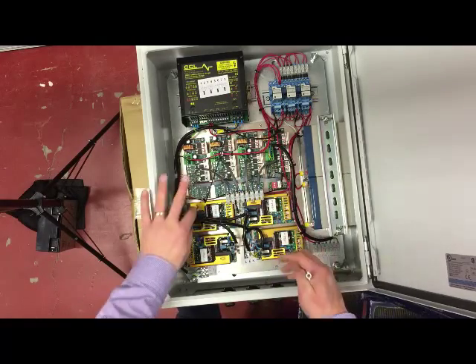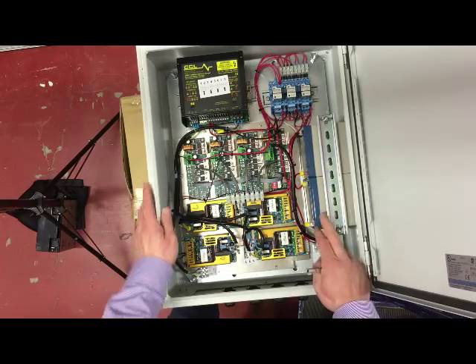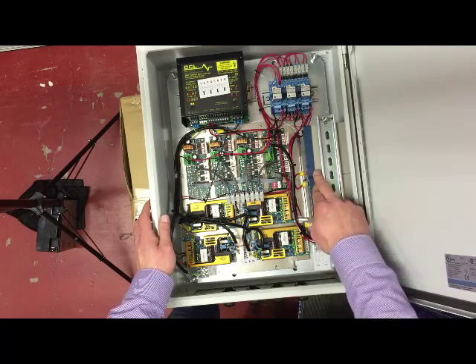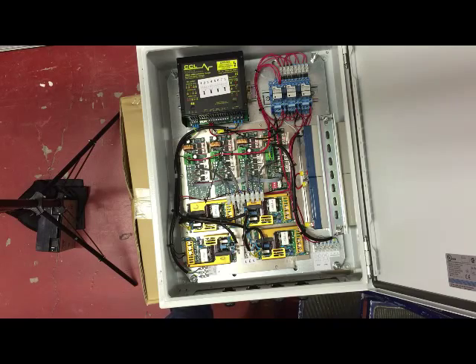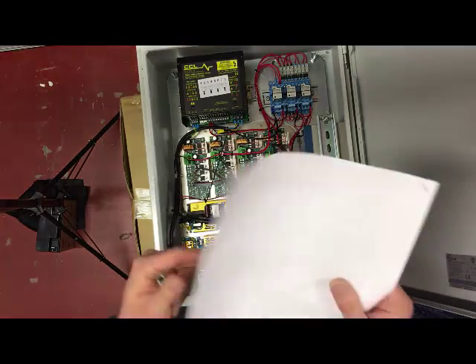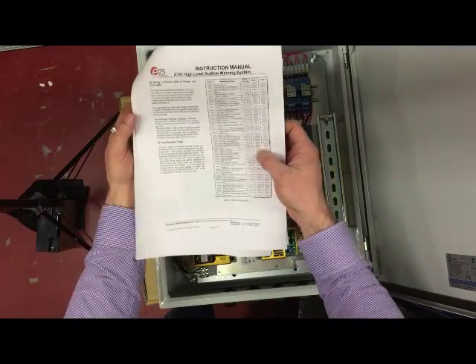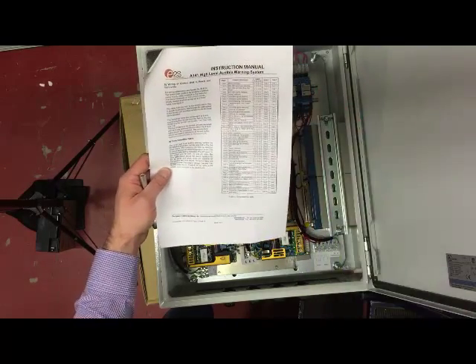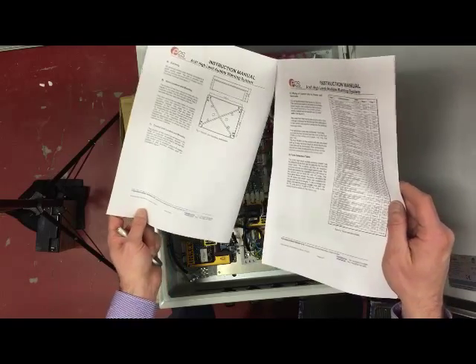It's fairly obvious where the terminations go in - it's obviously polarity sensitive. We have our drivers out to the 100-watt sounder units on each individual one, and we have the battery backup so if the power fails we carry on. These dip switches here are used for selecting the different tones. The manual gives us a full list of the 45 tones, and by setting the different dip switches you can achieve the different sounds you need.